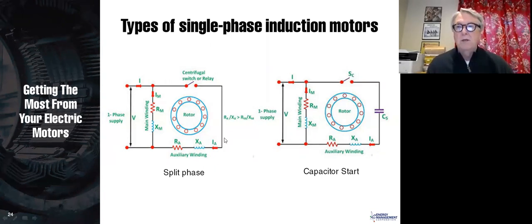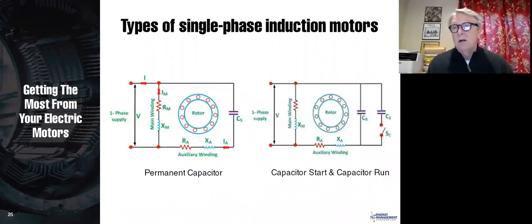Now, as we mentioned, that's only one of the 5 different types of single phase starters. I shouldn't say a starter, but the 5 ways in which we can design a motor to be able to start on single phase. The best is capacitor start, capacitor run, which gives you the most starting torque and your best power factor and efficiency, but it's also the most expensive. So that would be a split phase.